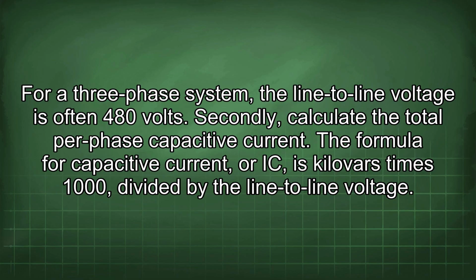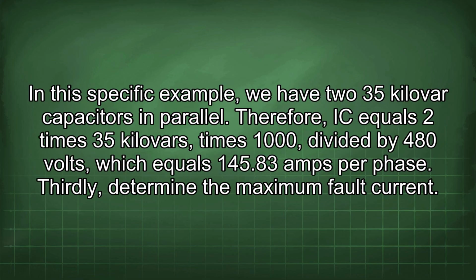Secondly, calculate the total per phase capacitive current. The formula for capacitive current, or IC, is kilovars times 1000 divided by the line-to-line voltage. In this specific example, we have two 35 kilovar capacitors in parallel. Therefore, IC equals 2 times 35 kilovars times 1000 divided by 480 volts, which equals 145.83 amps per phase. Thirdly, determine the maximum fault current.